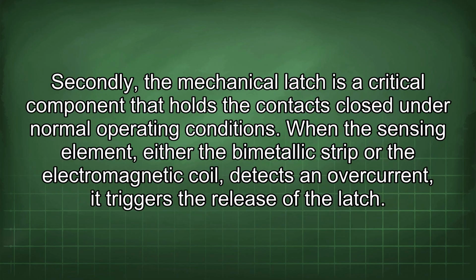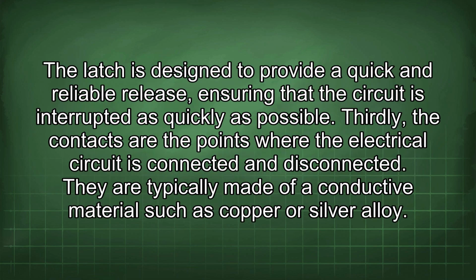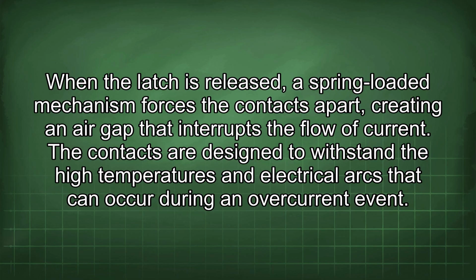Secondly, the mechanical latch is the critical component that holds the contacts closed under normal operating conditions. When the sensing element, either the bimetallic strip or the electromagnetic coil, detects an overcurrent, it triggers the release of the latch. The latch is designed to provide a quick and reliable release, ensuring that the circuit is interrupted as quickly as possible. Thirdly, the contacts are the points where the electrical circuit is connected and disconnected. They are typically made of a conductive material such as copper or silver alloy. When the latch is released, a spring-loaded mechanism forces the contacts apart, creating an air gap that interrupts the flow of current. The contacts are designed to withstand the high temperatures and electrical arcs that can occur during an overcurrent event.